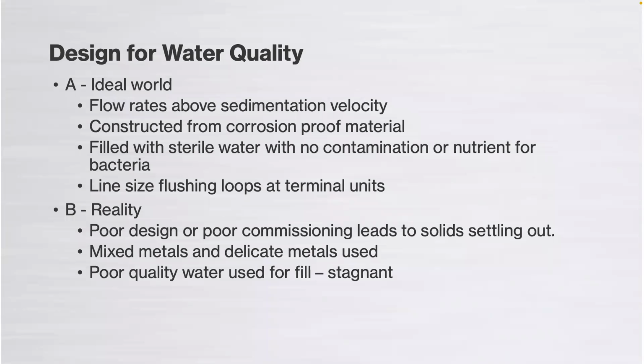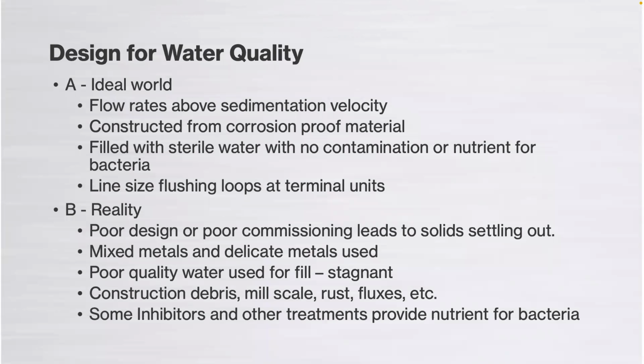Mixed metals and delicate metals are typically used on a system, and sometimes you can have poor water quality used. So it might be used from a mains water supply onto a project, onto a construction site that it's not being used. Somebody's tapped into a hydrant or something, and that's been sitting there as a dead leg for some time. And of course, construction debris, mill scale rust, fluxes, and so forth.